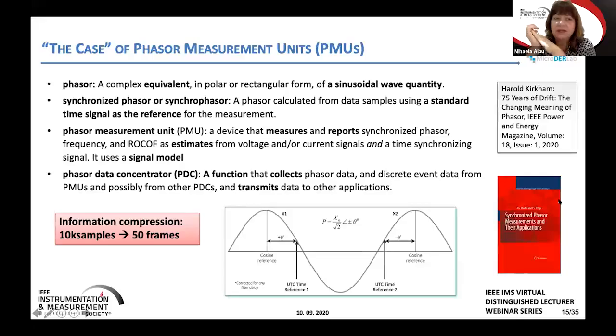The most important thing when we speak about the phasor measurement unit, as we start the case, is that it is again a measurement equipment using information compression, usually from 10 kilosamples per second as the sampling frequency - though some units use higher sampling frequency - down to 50 frames or 100 frames. Again, the example is for the 50 hertz system.